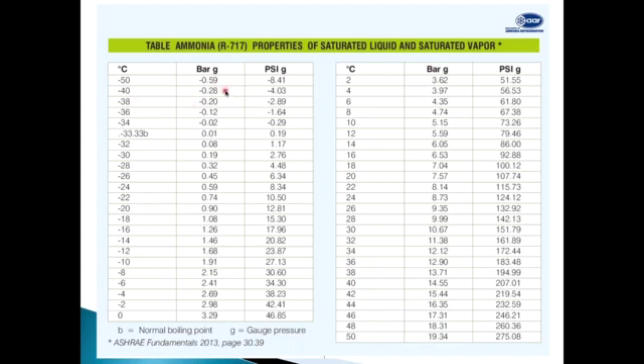This is very important. These charts are available everywhere. If anyone wants, you can always ask for AR and AR will provide you. But please remember throughout this presentation that the refrigeration system totally depends on this chart. When we say 38 degree condensing, our pressure has to be 13.71. If our pressure is higher, why the pressure is going to be higher, we will see. But remember, theoretically, the refrigeration system should work on this chart.